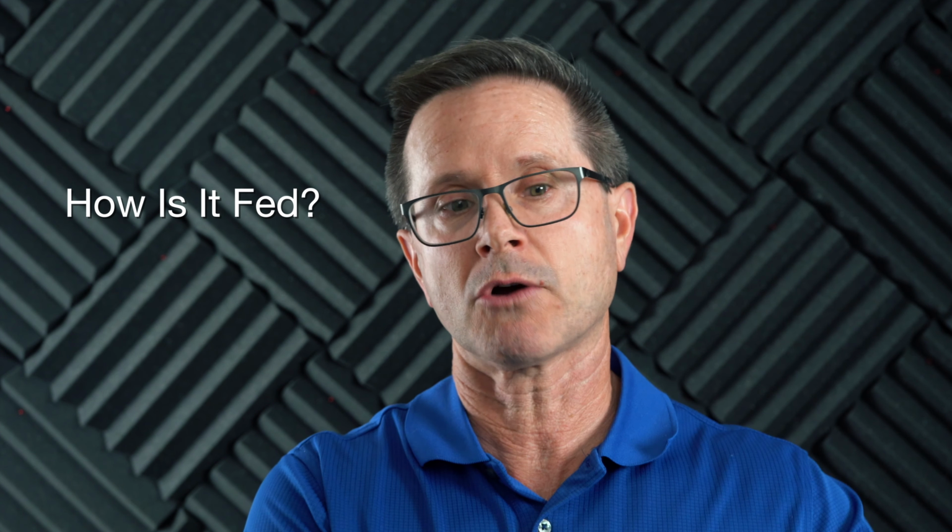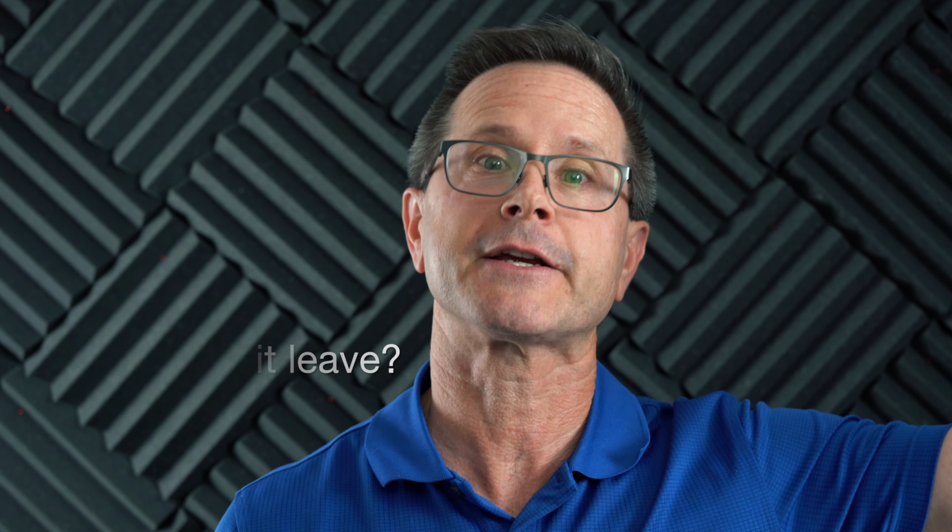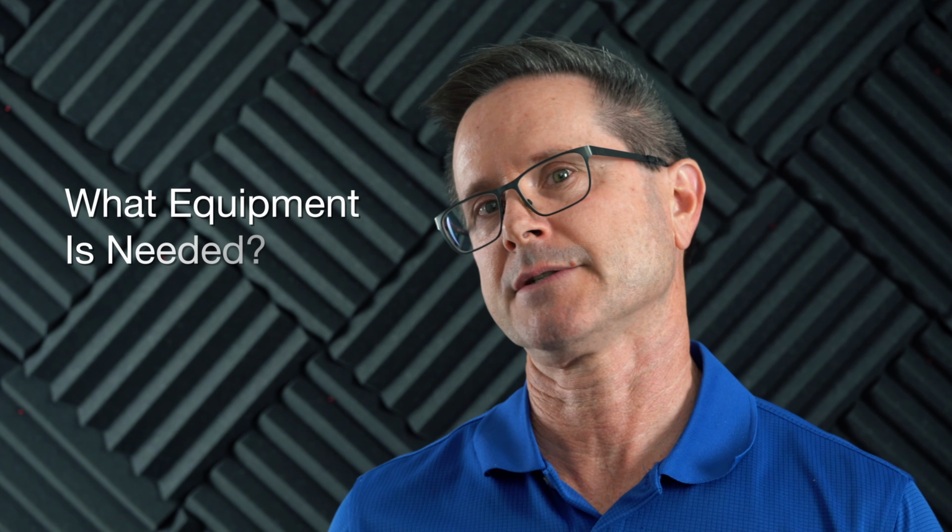That leads you to the second question you ask: how is it fed? Because once you know what's affected, then you get to a principle that we like to teach called line to load. How does it feed? How does it leave? If I've got light fixtures that are out, how are they fed? Well, I know it's fed from the lighting panel in the electrical room. So you'd go to the lighting panel, you would see if a breaker tripped, or you would check for voltage. If everything's good there, then you know somewhere between the breaker and the lighting fixture, you have a problem with the connection. So if you start by knowing what's affected, it leads you right to how it's fed.